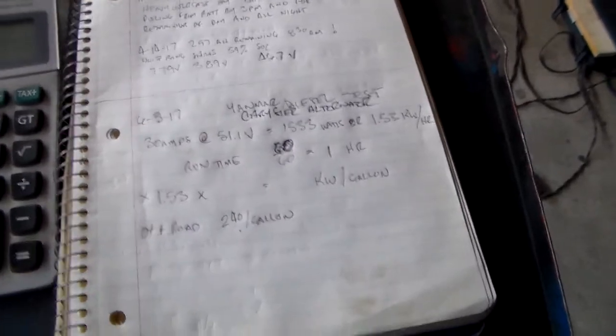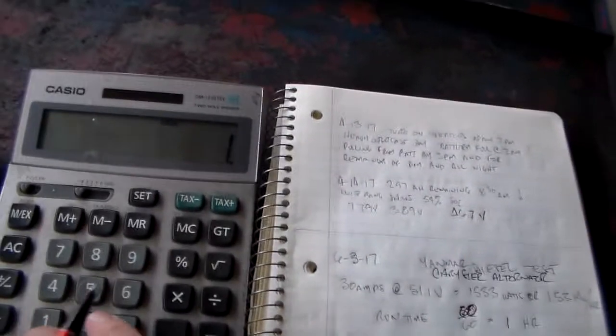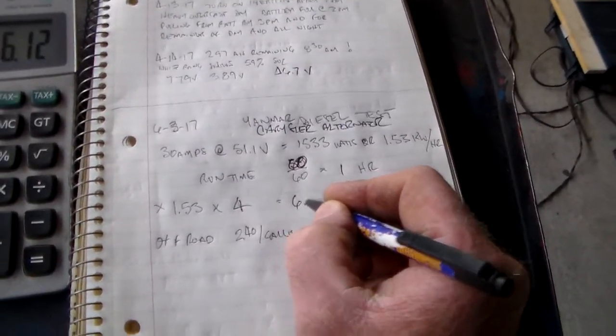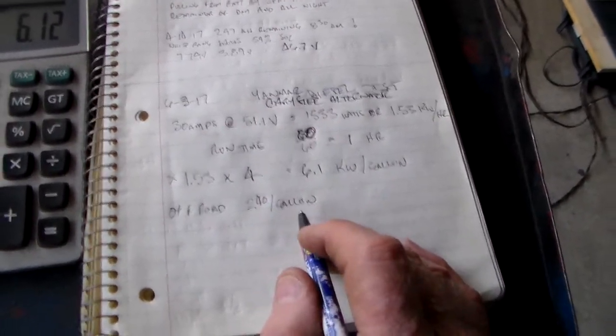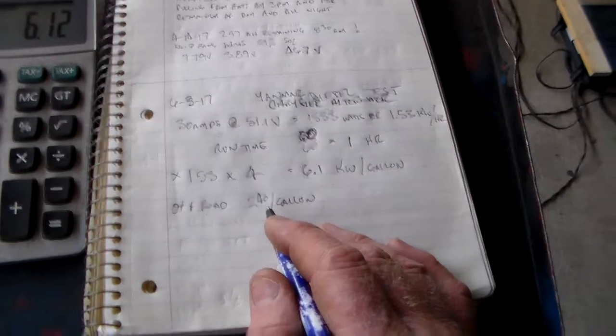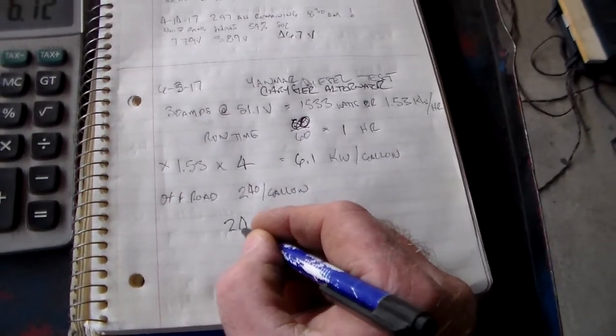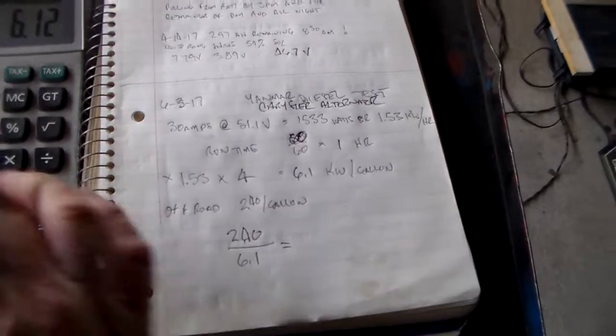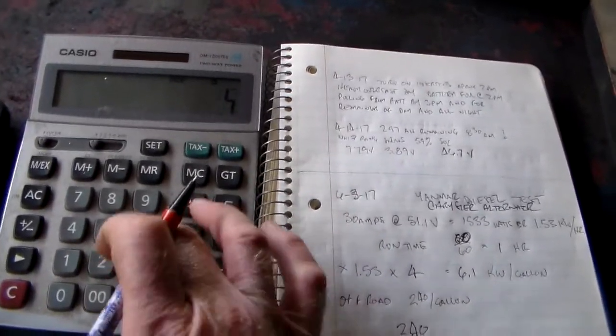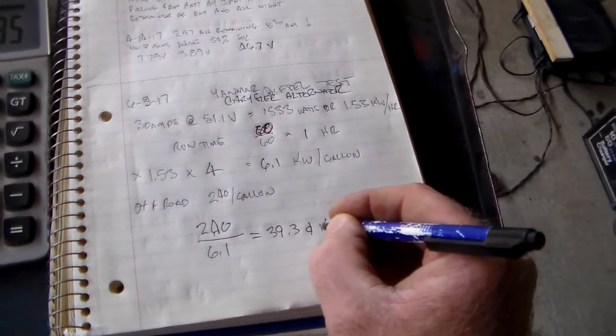We did that with a quarter of a gallon, so you would multiply that times four. Take 1.53 times four and you're going to get 6.1 kilowatts per gallon. I just called the local fueling station and their off-road diesel is $2.40 a gallon. If we take $2.40 and divide it by 6.1, it comes out to 39.3 cents per kilowatt hour.